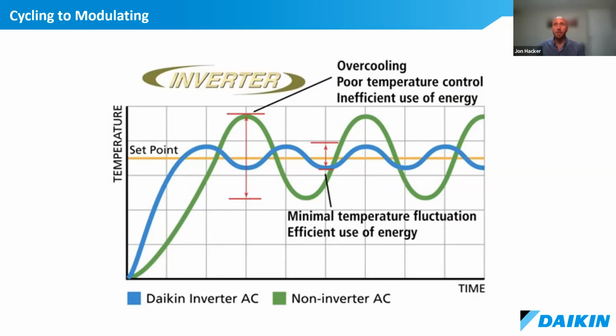So really what this is showing is it's comparing the single speed equipment in a green line and an inverter system with a blue line. Basically what we're showing here is that a traditional single speed system will fluctuate significantly more from the set point than an inverter system, right? With an inverter system, as it approaches that set point, it can modulate and slow down and more precisely control the delivery of heating or cooling so that it does a better job of maintaining comfort. Where the non-inverter system can only operate on or off. So it's going to operate on, it's going to overshoot set point, it's going to turn off, the temperature's going to drift further away from set point until it's kicked on again, right? So we have a much better temperature control with an inverter.